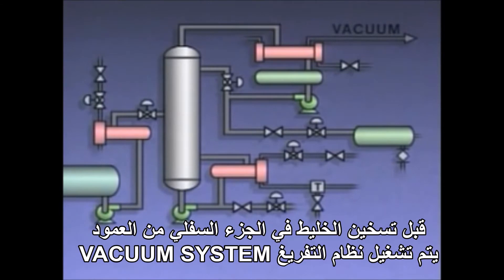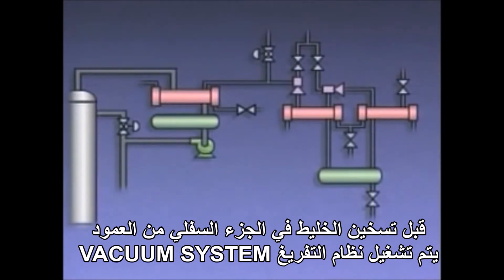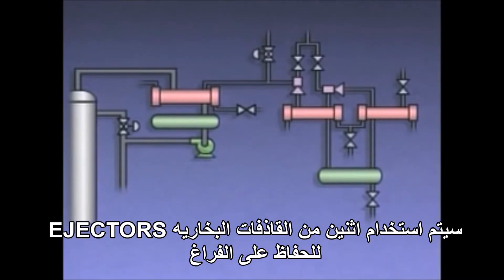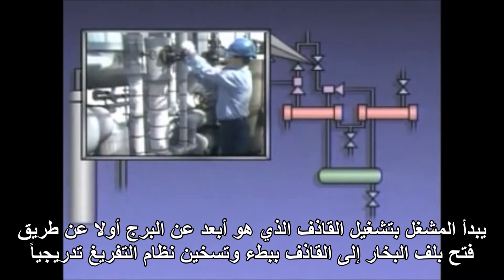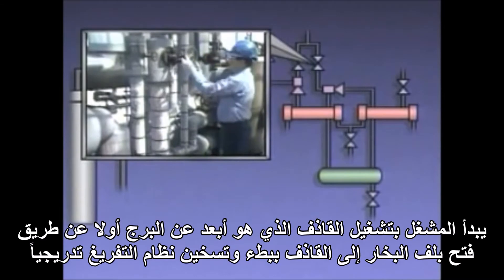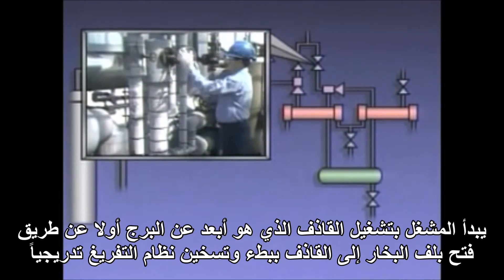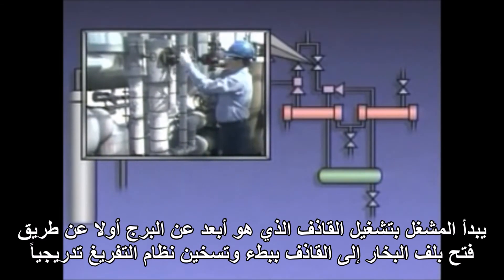Next, before the mixture in the bottom of the column is heated, the vacuum system is started up. In this system, two steam jets are used to maintain the vacuum. The operator starts the jet that's farther from the column first by slowly opening a valve, which admits steam to the jet and gradually warms the vacuum system.